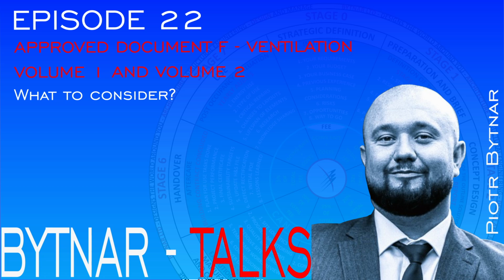What is the less airtight dwelling, you ask? It is a dwelling that leaks air more than 5 meter cubed per hour per meter squared at 50 pascals of pressure as designed, or 3 meter cubed as built. For highly airtight dwellings, mechanical ventilation may be the only solution. Depending on the ventilation approach, you will take the different limits of ventilation minimums which are prescribed by the guidance.